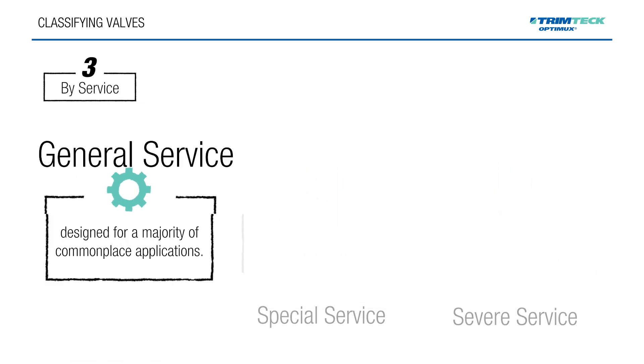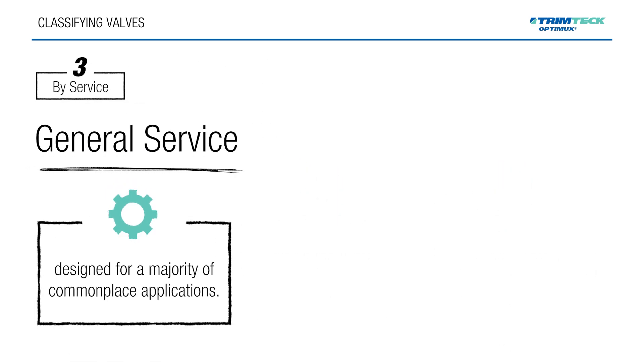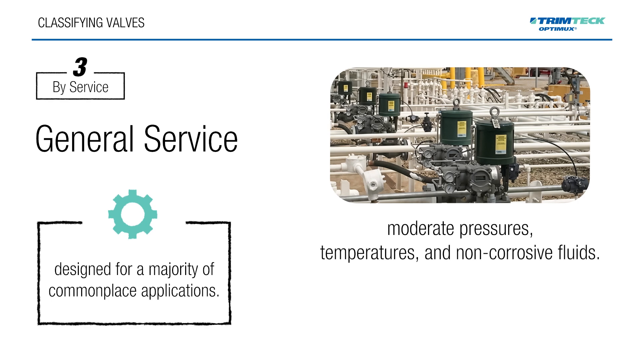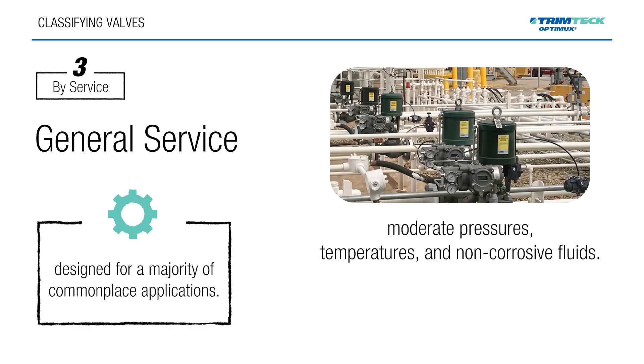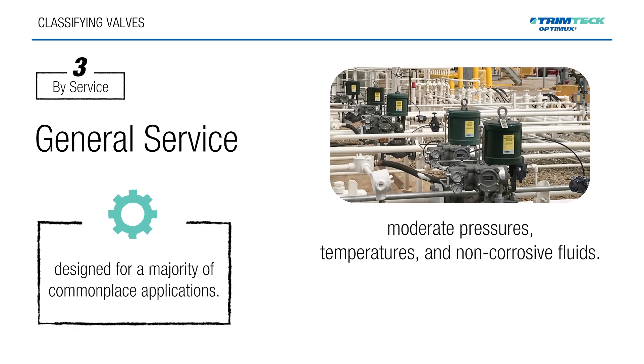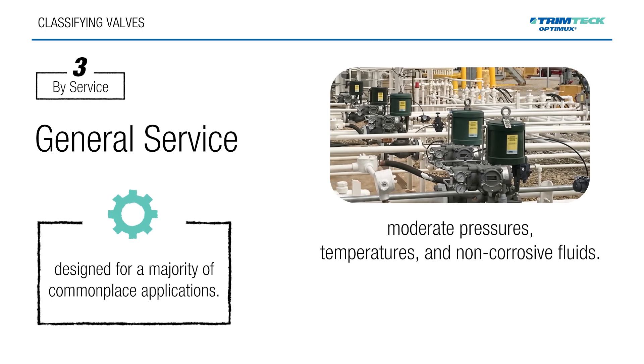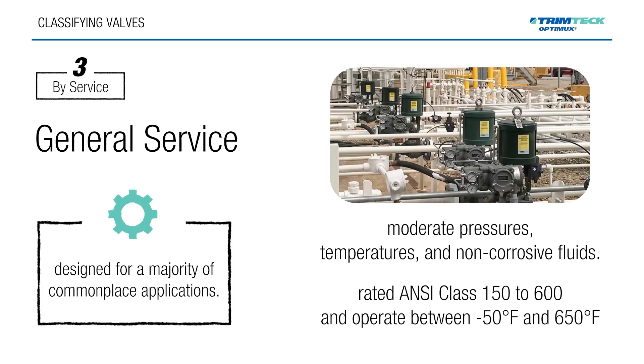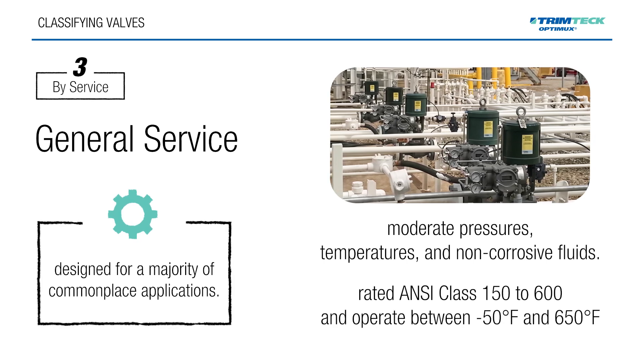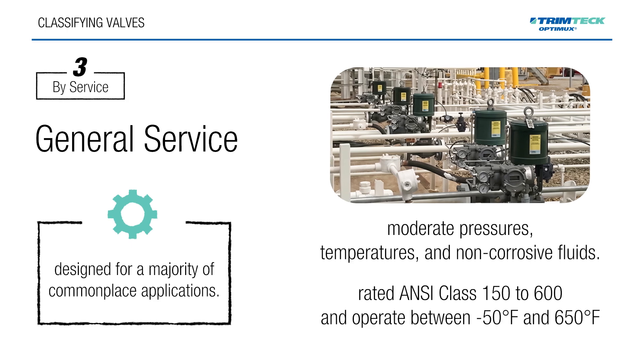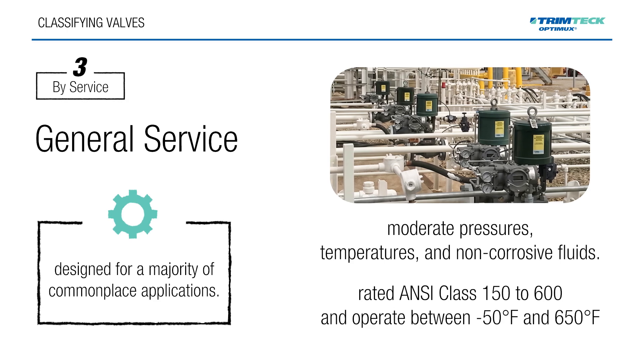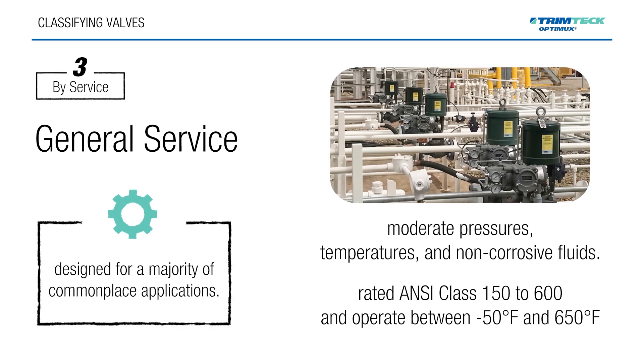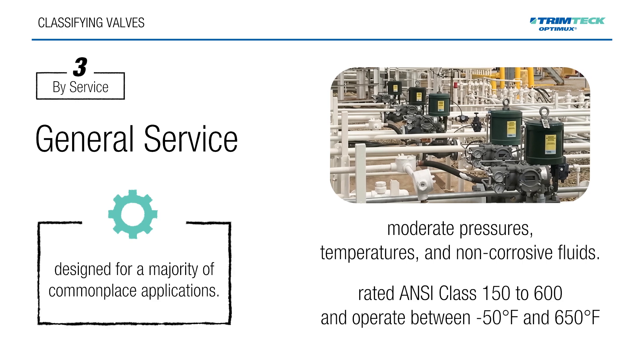General service valves are designed for moderate pressures, temperatures, and non-corrosive fluids. These are commonly rated ANSI class 150 to 600 and operate between negative 50 degrees Fahrenheit and 650 degrees Fahrenheit, making them ideal for standard industrial applications.